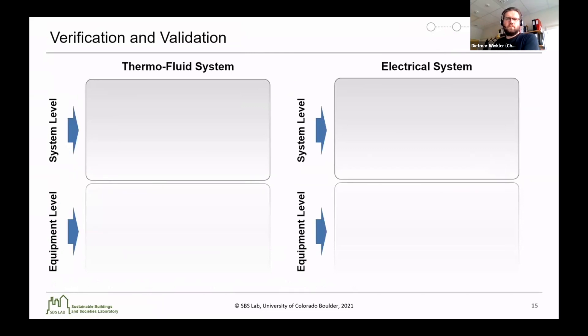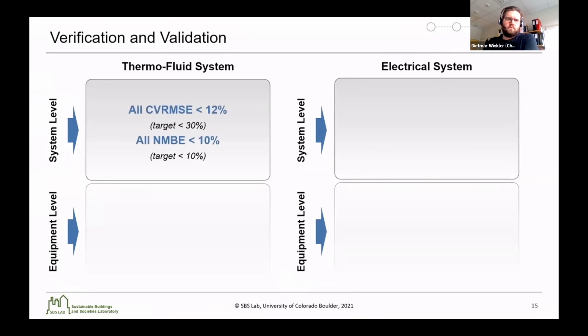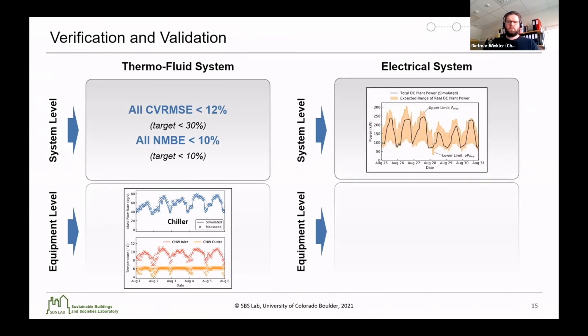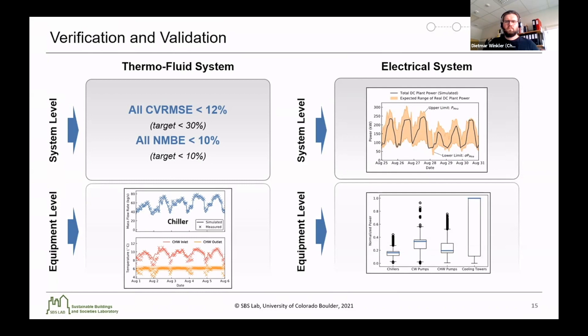For verification and validation, we looked across both thermofluid and electrical systems at both system and equipment levels. For the thermofluid system at the system level, we evaluated the coefficient of variation of the root mean square error and the normalized mean biased error to ensure all measured points were within industry standard targets. At the equipment level, we looked at a variety of equipment at different instances within the simulation, and for the chiller as an example, the simulation and measured data matched very well. For the electrical system at the systems level, we set upper and lower limits for the measured data and verified that the simulation always remained within those expected limits — this was necessary because the system does not have electrical submetering and the plant also provides other functions including district heating.